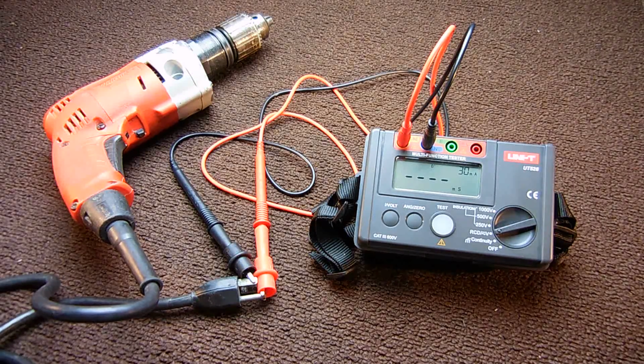panel. Now, before any insulation testing takes place on a breaker panel, you have to ensure the branch circuit that you're checking, or even the feeds into the panel, if you wanted to check those, must have all power removed. The circuit cannot be on, so you have to make sure you disconnect the wires from the circuit breaker if you'd like to check a branch circuit. Also, anything connected to that branch circuit must be removed from the electrical receptacle. So if you have a clock plugged in, a computer, or anything else, it must be removed from the circuit.